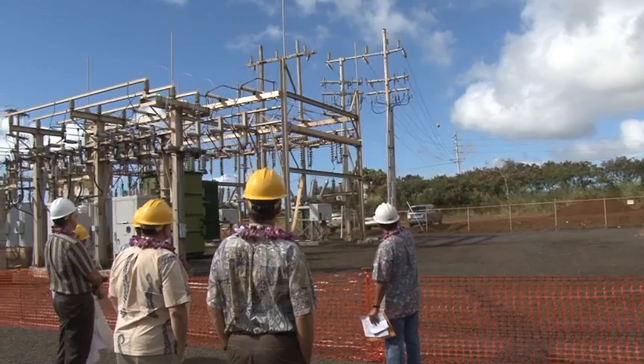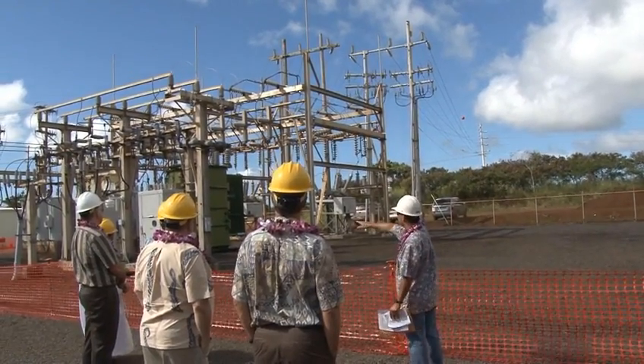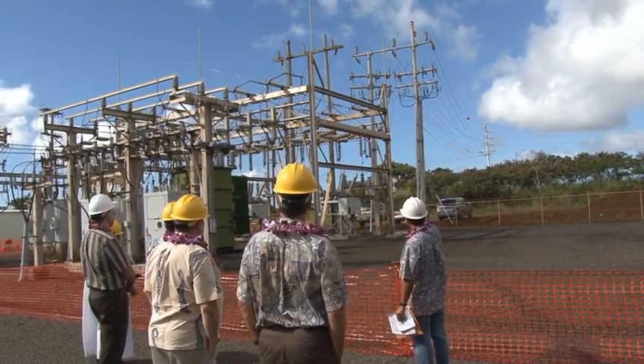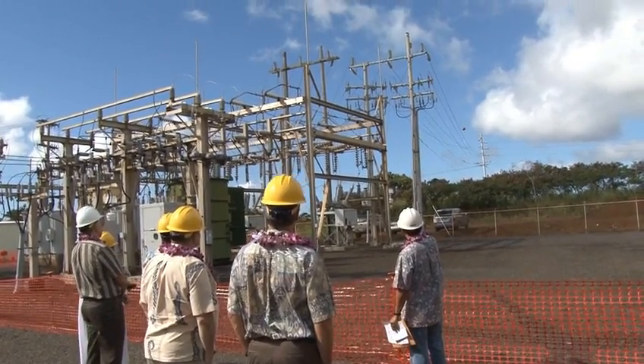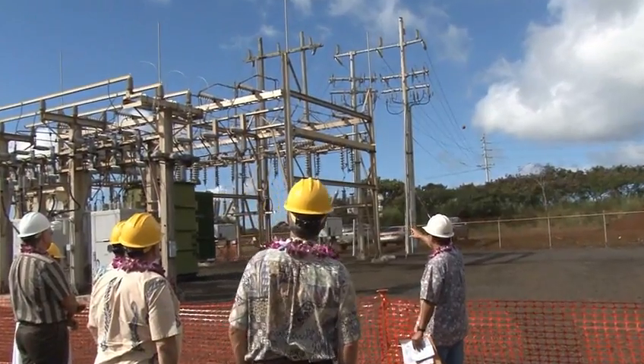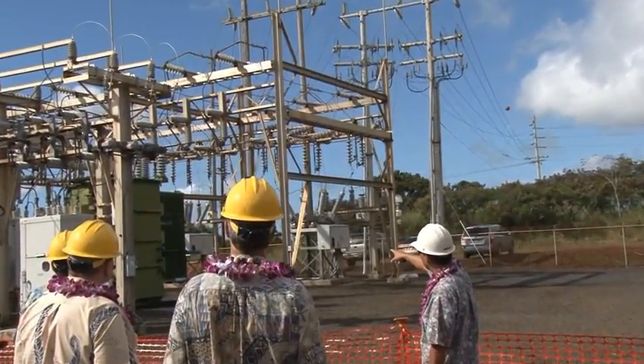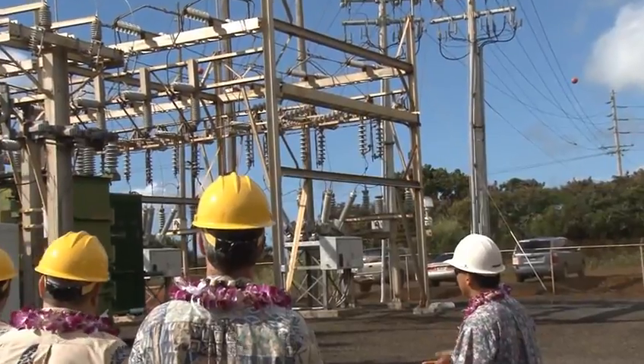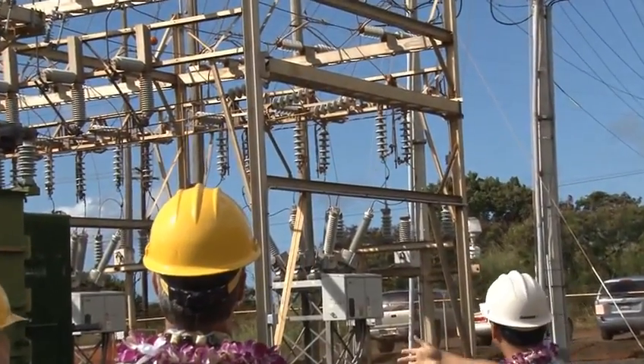So the bigger breakers, which are a larger version of the small breakers here, are actually the transmission breakers. So they're there to protect the system. And then, of course, they come in through this bus, step down to these power transformers, the green and yellow ones, to a lower, more manageable voltage. And of course, it goes to the breaker over here.